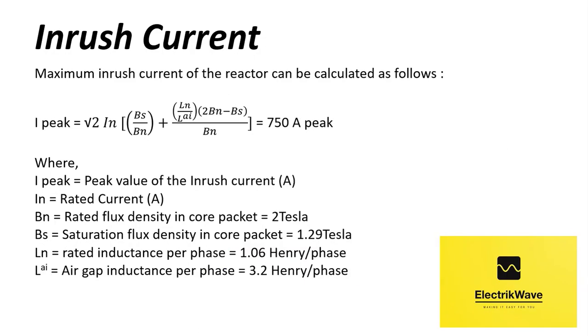Maximum inrush current of the reactor can be calculated as per the given formula, where I_peak equals peak value of the inrush current in amperes; I_n equals rated current in amperes; B_N equals rated flux density in core packet equals 2 tesla; B_S equals saturation flux density in core packet equals 1.29 tesla; L_N equals rated inductance per phase equals 1.06 henry per phase; L_AI equals air gap inductance per phase equals 3.2 henry per phase. So, for the 120 MVAR, 420 kV shunt reactor, maximum inrush current would be 750 ampere peak.